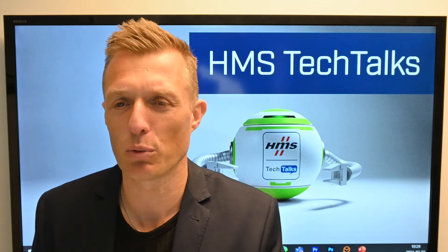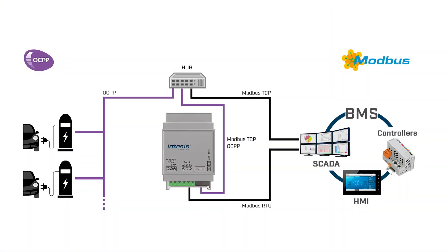So if we get a little bit more technical, how does it actually work when you translate the different standards? What do you need to do to set it up? Well, if we are looking at the OCPP standard, we can use a Modbus gateway — an OCPP-to-Modbus gateway — to enable that communication between the BMS and the charging point. In the OCPP technology, you need to have a central system and a charging station. When we place a gateway there, the gateway together with the building management system becomes a central system in the OCPP installation.